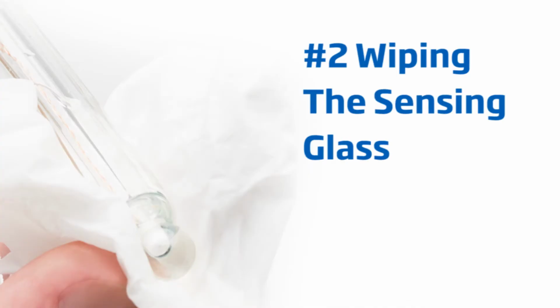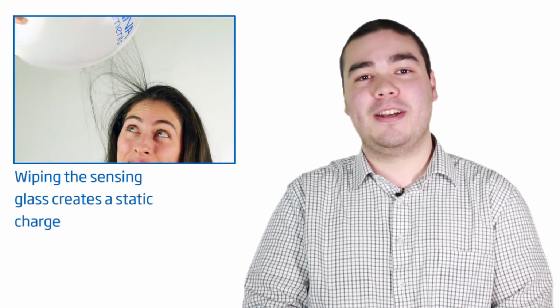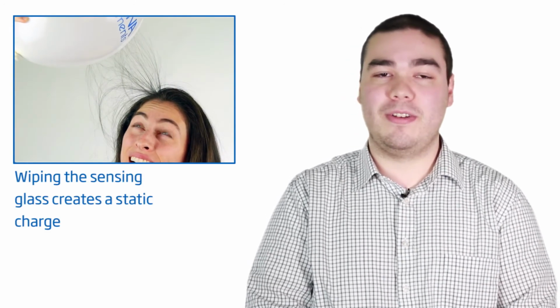Number 2 is also a very common mistake, wiping the sensing glass. As we've already discussed, electrode bulbs are made from sensitive layers of glass. Wiping the electrode wears on these layers and creates a static charge that interferes with the voltage reading of your electrode, giving you wrong readings. To clean the electrode, rinse it in distilled water.